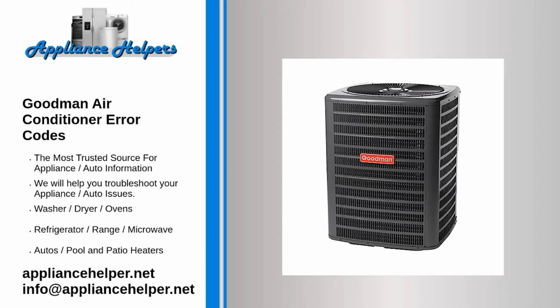Code D2, problem: the air conditioner heat pump is wired as part of a communicating system and the outdoor unit requires airflow greater than the indoor unit's airflow capability. Shared data is incompatible with the system or missing parameters. Code D3, problem: shared data sent to the integrated control module does not match the hardware configuration. Code D4, problem: shared data on the memory card has been rejected.